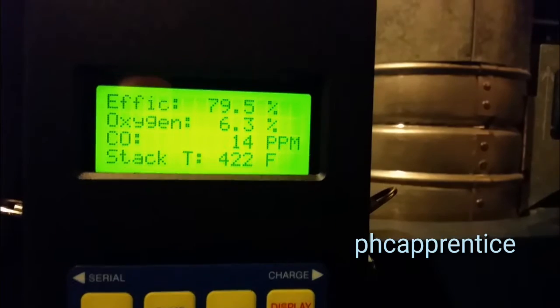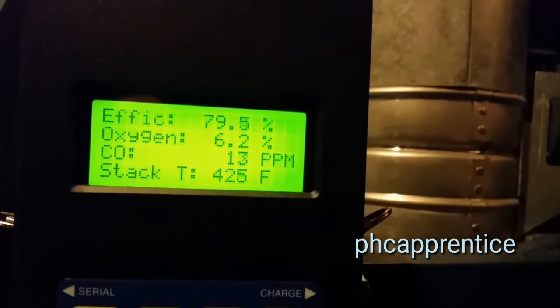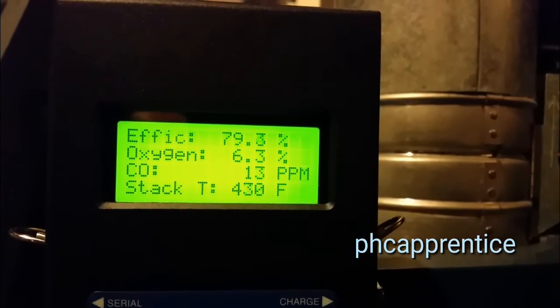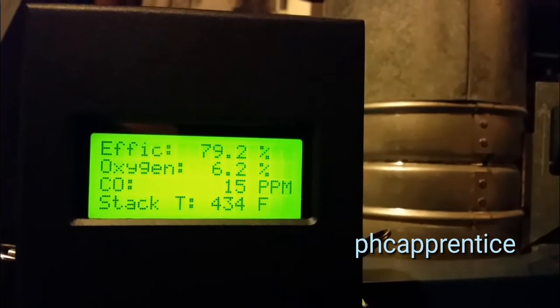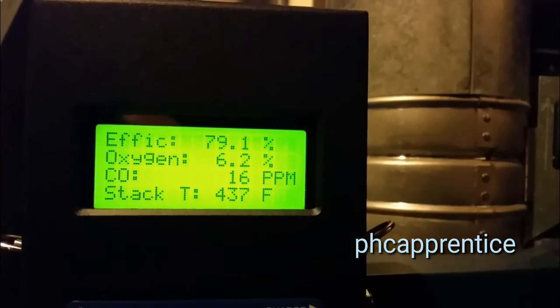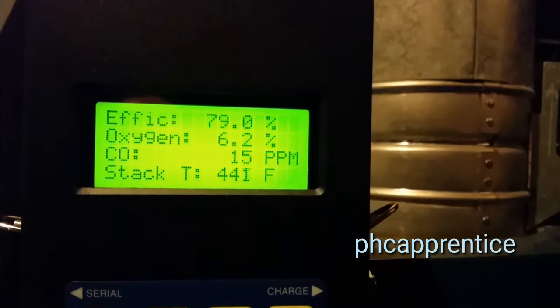Stack temperature is climbing. This boiler usually has a stack temperature of around 5 something, which is not absorbing the heat as well as it should. It could be a pump issue, it could be a slightly dirty heat exchanger, it could be sludge inside the boiler.